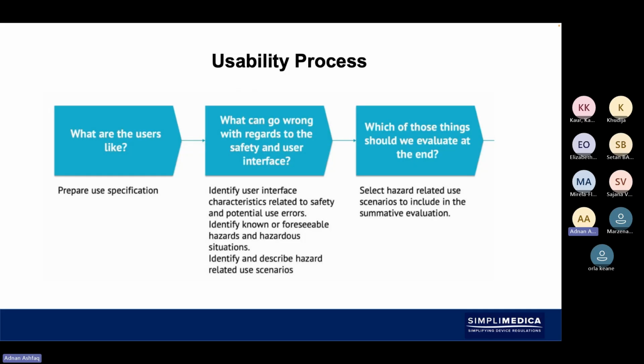If you need to identify any characteristics, again, this should be identified in your risk analysis. So you would identify user risks. Which of those things should we evaluate at the end? Look at the hazards that are coming from the usability and the user interface. What's really useful to do, when you have a use risk analysis that you're developing, is think about doing a step-by-step user flow diagram, which then breaks down the use of the device in stages.